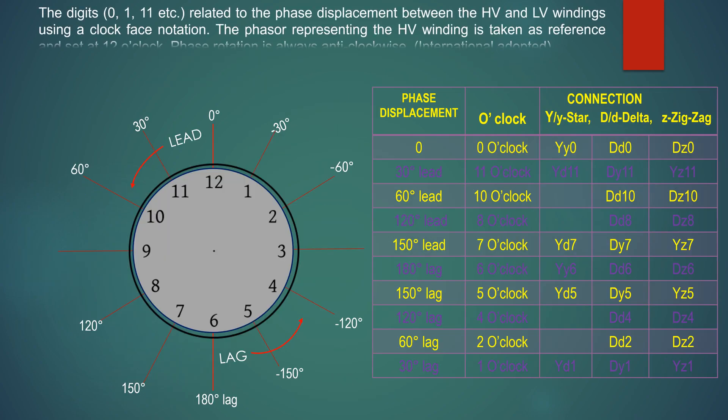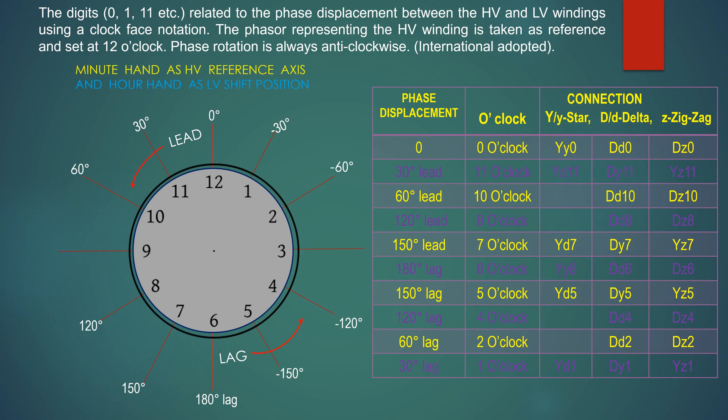The digits 0, 1, 11, etc. relate to the phase displacement between the HV and LV windings using a clock face notation. In the phasor representation, the HV winding is taken as reference and set at 12 o'clock.